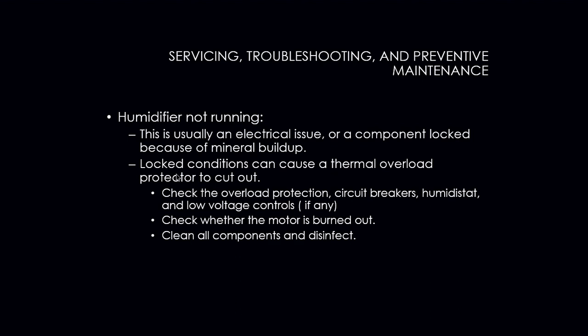Okay, if we are running into problems with humidifiers that are not working, or we're doing maintenance on these things, we've got to look at a couple of issues. A lot of our humidifiers are going to have a humidistat. That humidistat is going to be wired to a solenoid and probably the motor on the humidifier. So once the humidistat calls and closes, we need to energize the solenoid so that we can open up the water line that's connected to the humidifier, and it's also going to turn on the motor inside there, if there is one, before anything can happen. Okay?